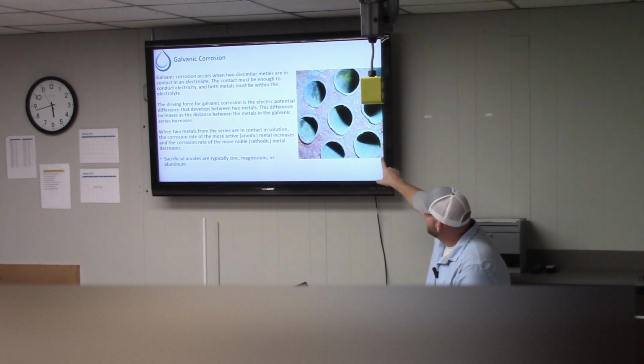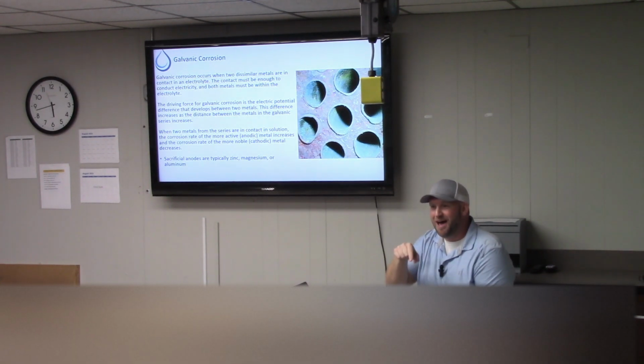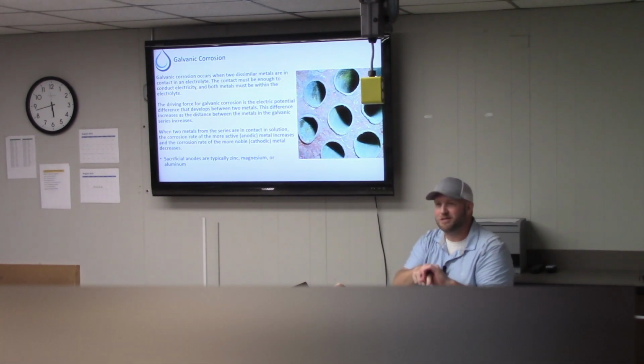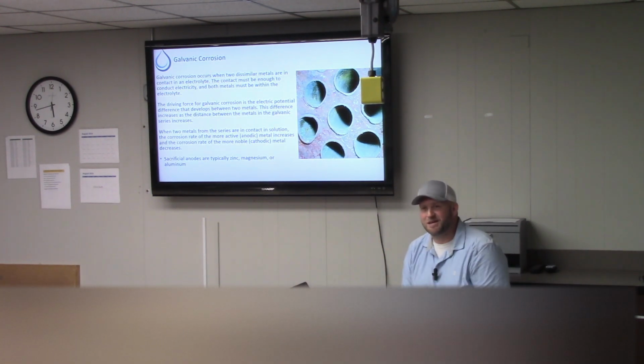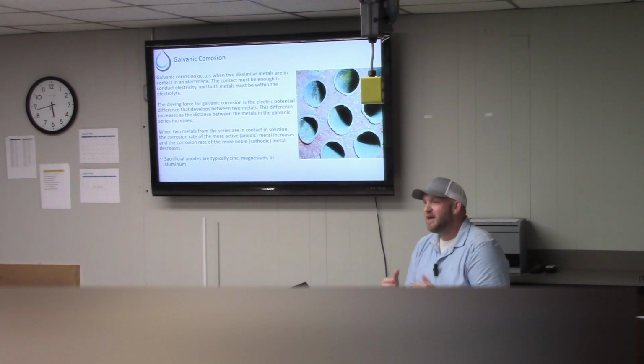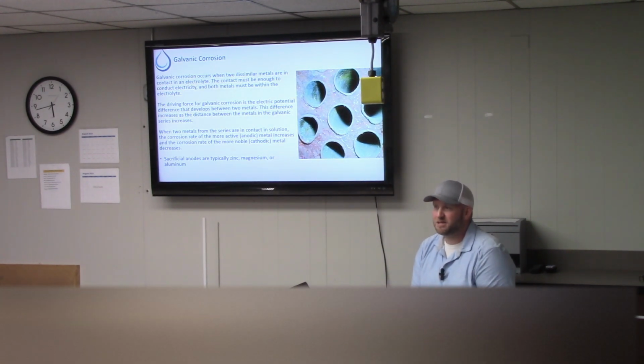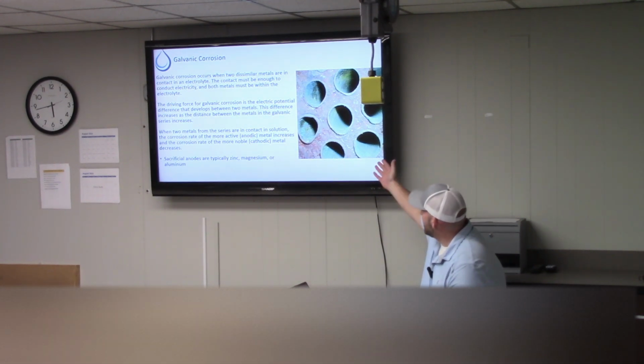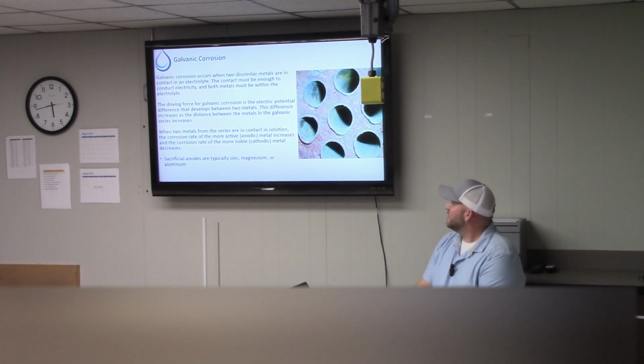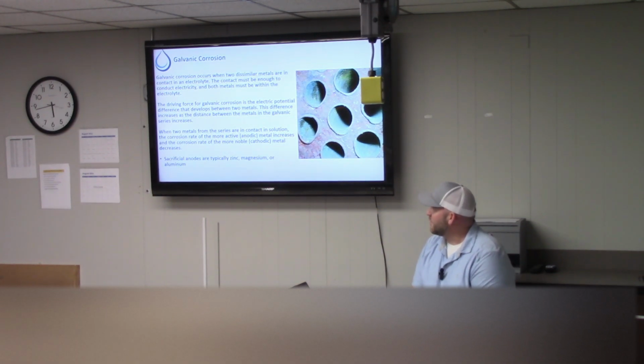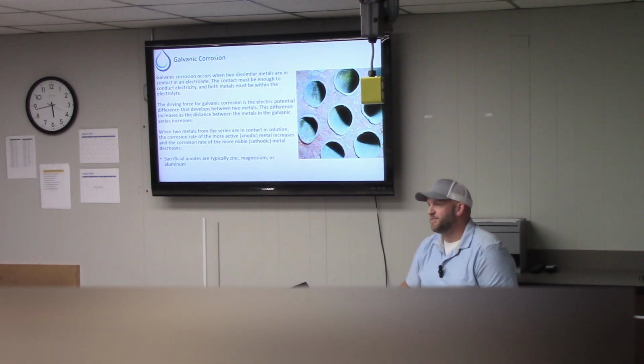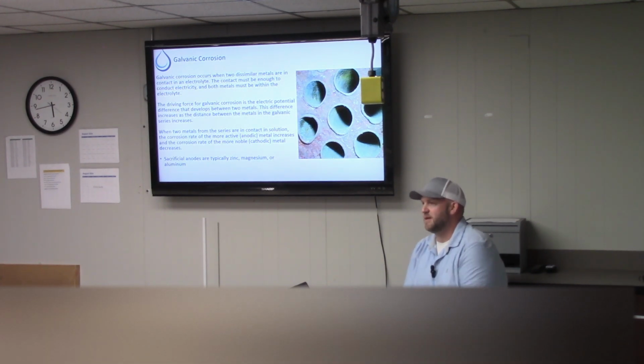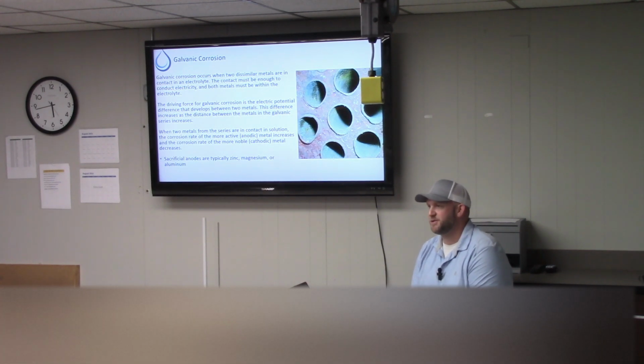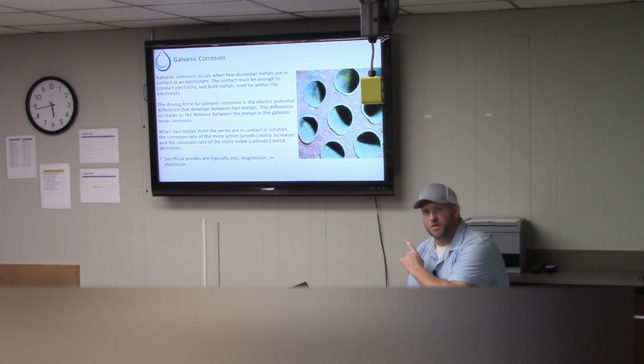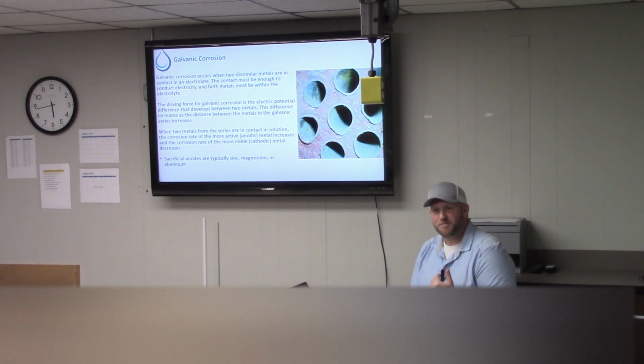When that copper lands on the steel, in that spot, it starts drilling through the steel. That's this corrosion mechanism in a nutshell. It is terrible, and it's insidious, and it's awful, just as bad as pitting, because really, we're creating pitting. This is why when we look at corrosion of yellow metal in a system, we can't just focus on the chemistry being the only thing that solves that issue. It goes back to velocity as well. One of the other things that we talked about.